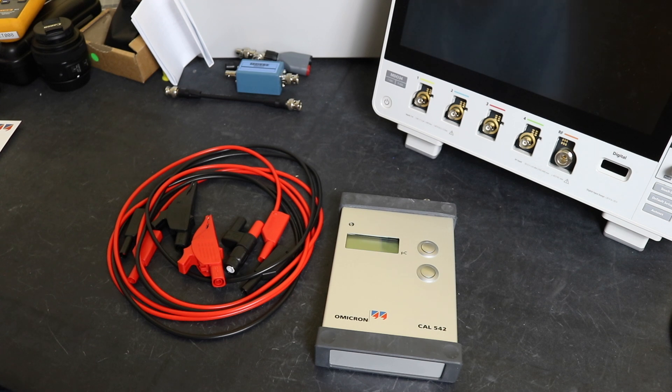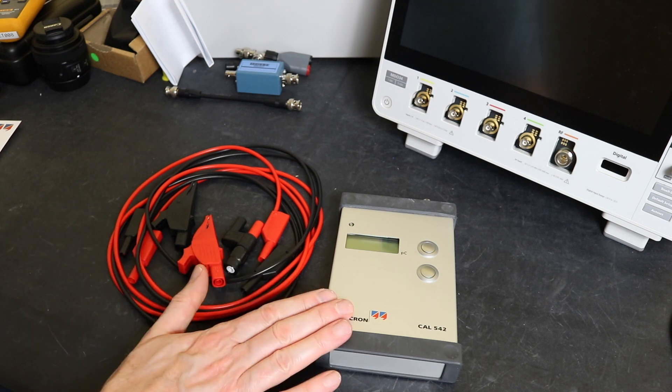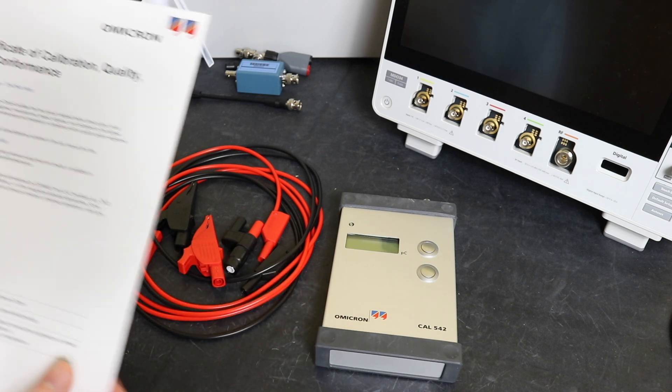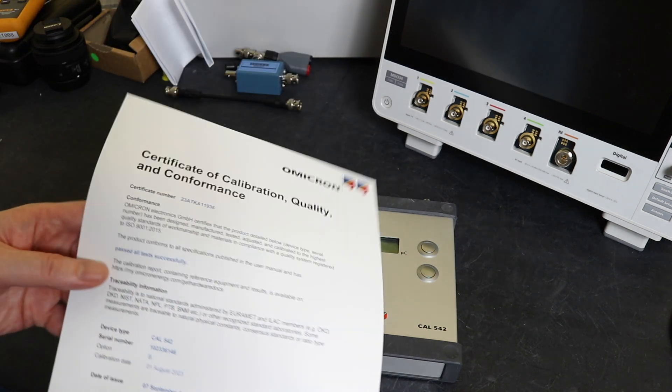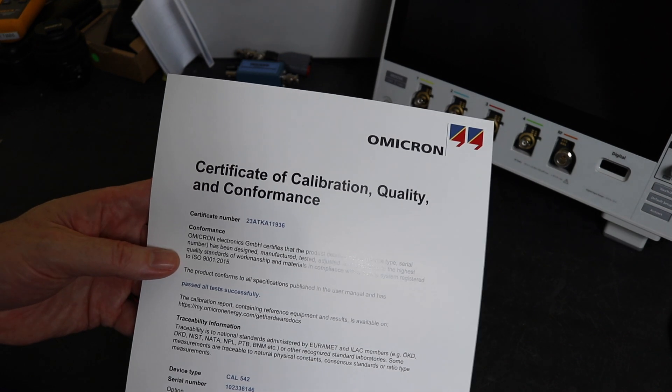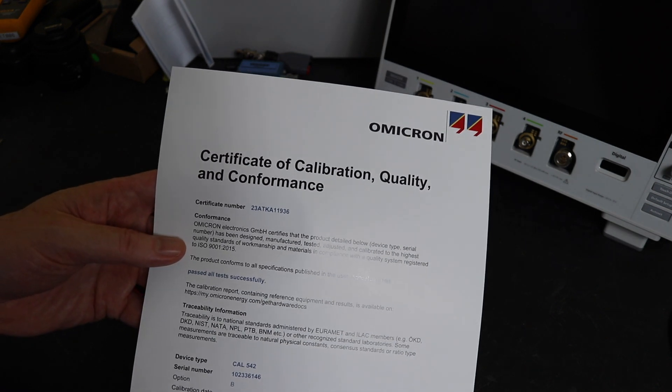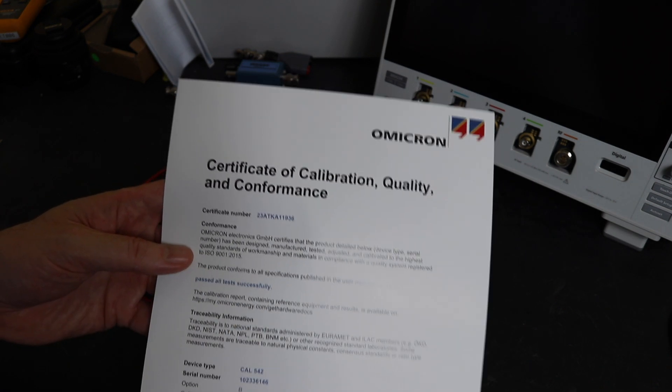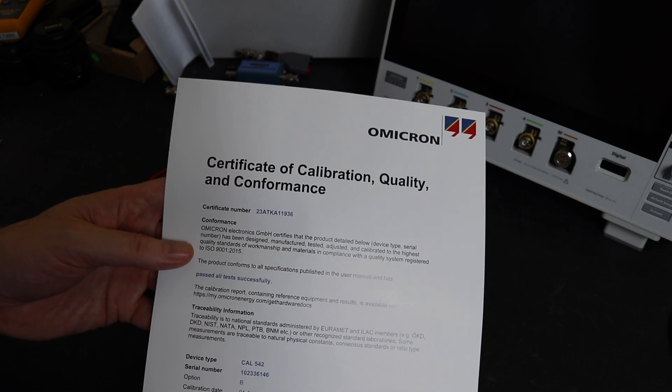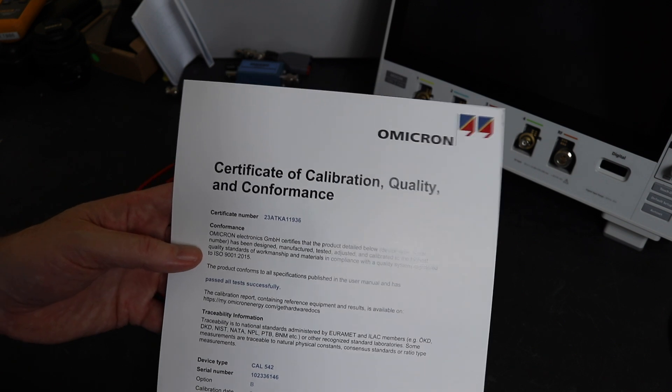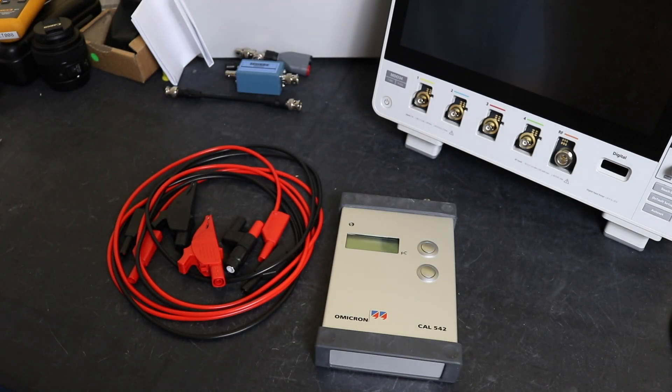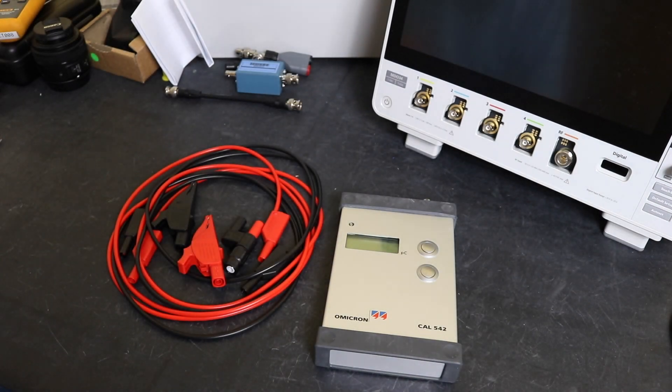This particular unit comes from Omicron with this certificate of calibration/conformance. But you see here there's no data on here, there's no numbers or anything, it's just a statement to say yes they have tested it, which isn't really good enough for me. I don't like that kind of approach.